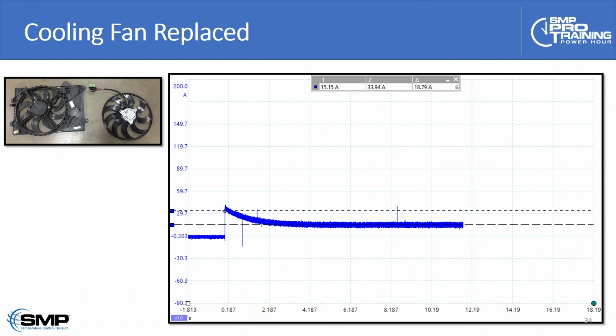With the fan replaced, you can see the initial current spike is dramatically less. It only gets to about 50 amps on that initial spike and then settles down to around 25, 30 amps. This is why it's very important to check.